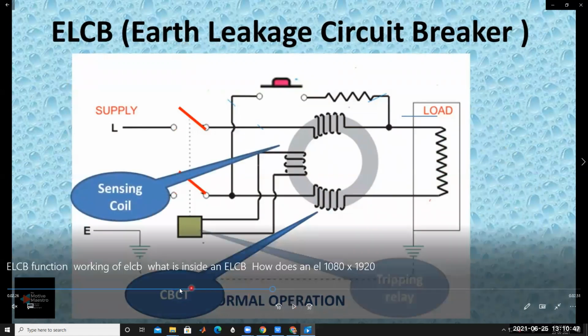So this is called CBCT. These are the different parts. CBCT, core balance current transformer. This circular one is called the core balance current transformer. This is called the sensing coil. These are called operating coils, and this is also called an operating coil, but this is called the sensing coil. Okay, the relay. This is called relay or sensing coil.